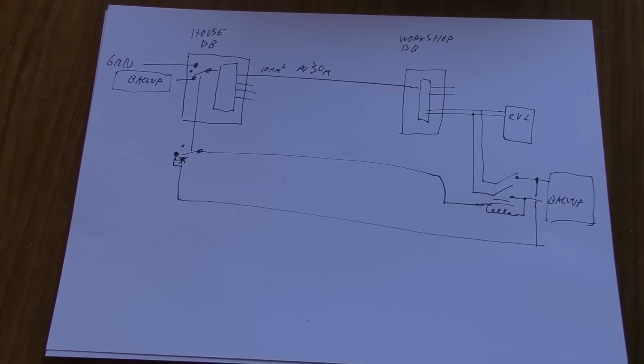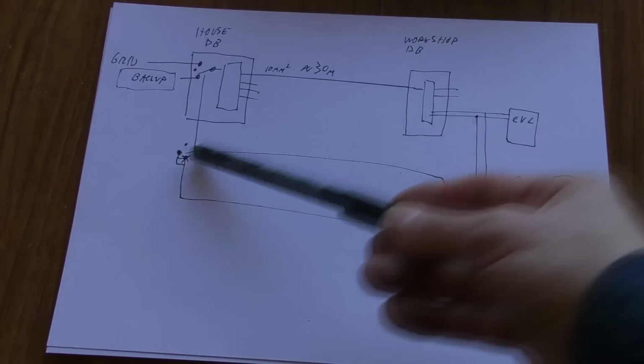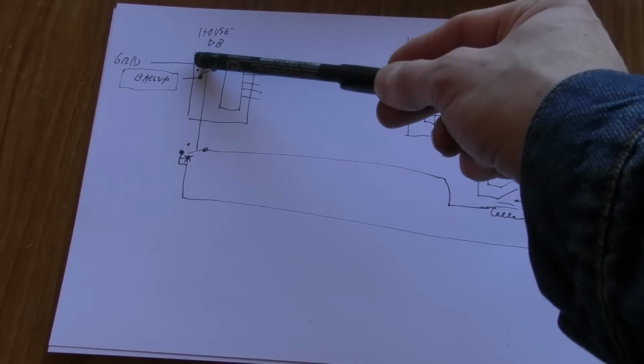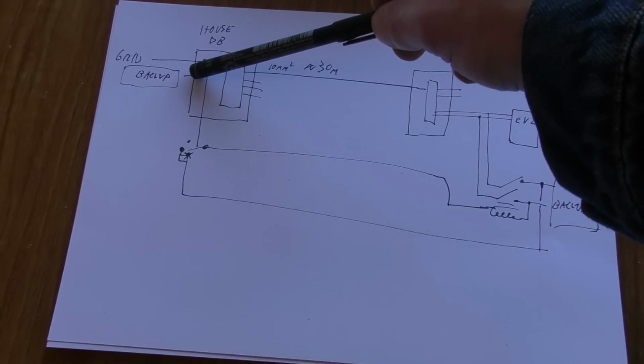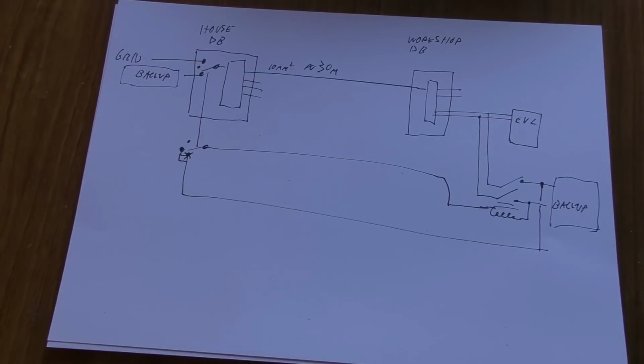So I spent a bit of time thinking about that, and I think about the only sensible way to do that would be to have a contactor here at the workshop end, which is powered from the backup side, but with an interlock connector. I need to have a low current wire that runs back to this distribution board with a switch which only closes when this is in its center off position, because obviously if it was to close when it was connected to that local backup connector, then the pins on that backup connector would be live, which you don't really want.